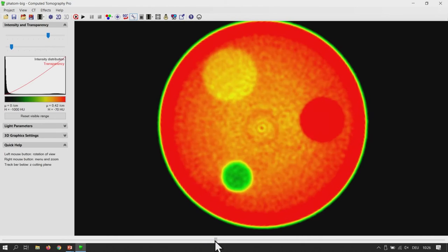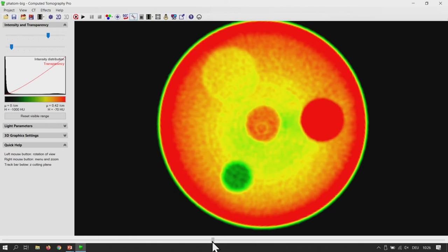In the next layer we are talking a little bit more about absorption coefficients. And going back to history, this system of computer tomography was developed by a man called Hounsfield, and named after him is a Hounsfield unit, which is a measure for the absorption coefficient. Physics just calls it absorption coefficient, to be measured per centimeter, and Hounsfield is more for the medical guys, talking about Hounsfield units. And in the upper right you can see a display where the computer shows me what is right underneath the mouse cursor. And in this layer we have our plastic material, which is polyoxymethylene, in the hole we have a patch of air, a patch of polytetrafluoroethylene, Teflon, and a patch of polymethyl methacrylate, perspex glass.